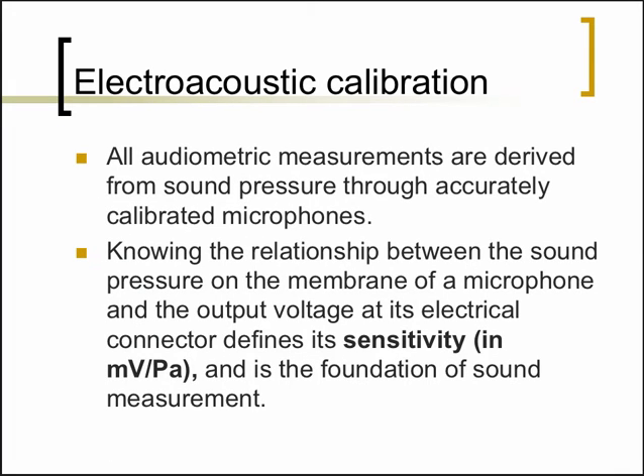So for the most part of this annual calibration, one would be working with a calibrated microphone. So again, a microphone is a kind of transducer, and transducers are devices that convert one form of energy to another form. In this case, microphones convert acoustical energy into electrical energy, which then is read by a sound level meter, and so the main aspect of this microphone would be knowing the relationship between the input to the microphone and the output of the microphone.